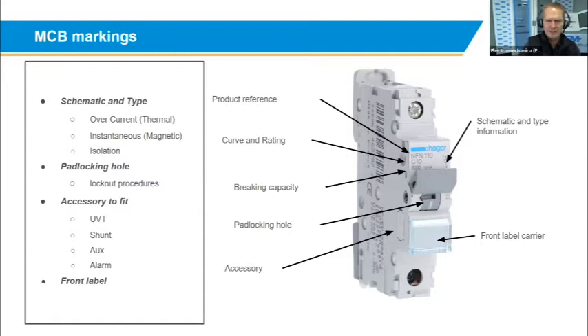Then the padlocking device, obviously we'll know that will be for lockout procedures. The nice thing about the product is that you can lock it out in the on position and in the off position. So now you will ask me, why do you want to lock a circuit breaker in the on position? That is for critical equipment where you don't want somebody to physically switch off the product by accident or on purpose, you never know. You can lock it out in the on position, but keep in mind that the product will still trip inside, although the toggle is in the on position. So even if overcurrent or a short circuit appears in your system, the circuit breaker will internally still open safely and protect the installation.